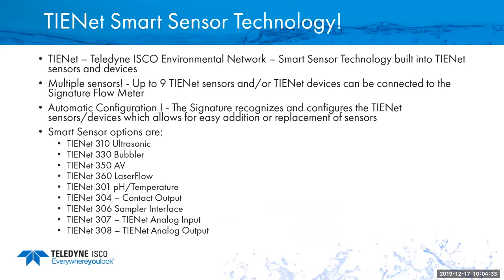What it is, it's our proprietary protocol of talking to each one of the sensors. With a signature meter, you can have up to 9 different sensors or devices tied into the signature meter using the TIENet bus. The automatic configuration speaks to the fact that you can install the sensors or wire them in and then do a scan to bring the sensors into the signature flow meter, and then you're able to program them. Some of the options that you can get are the 310 ultrasonic, 330 bubbler, 350 AV sensor, the 360 laser flow, 301 pH and temperature, 304 contact closure, 306 sample interface, 307 analog input, and the 308 analog output.